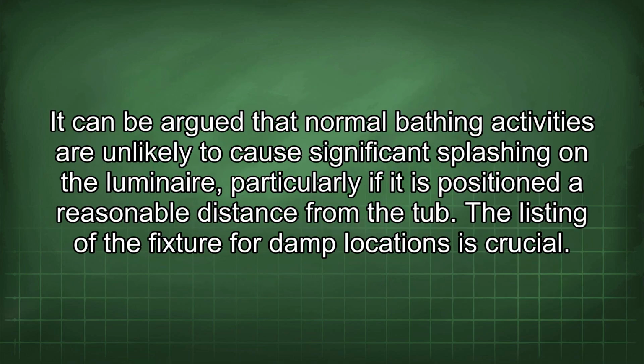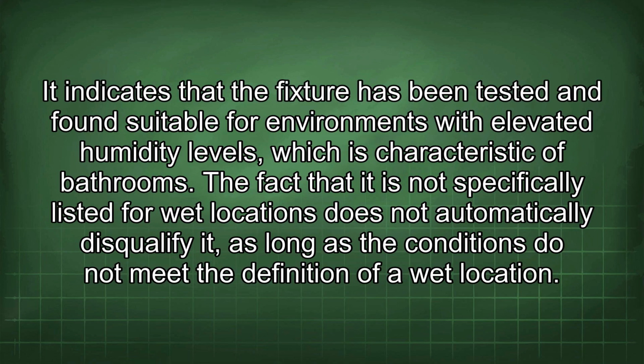directly. It can be argued that normal bathing activities are unlikely to cause significant splashing on the luminaire, particularly if it is positioned a reasonable distance from the tub. The listing of the fixture for damp locations is crucial. It indicates that the fixture has been tested and found suitable for environments with elevated humidity levels, which is characteristic of bathrooms. The fact that it is not specifically listed for wet locations does not automatically disqualify it, as long as the conditions do not meet the definition of a wet location.